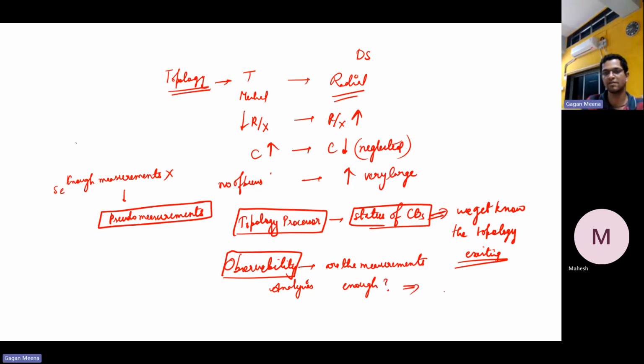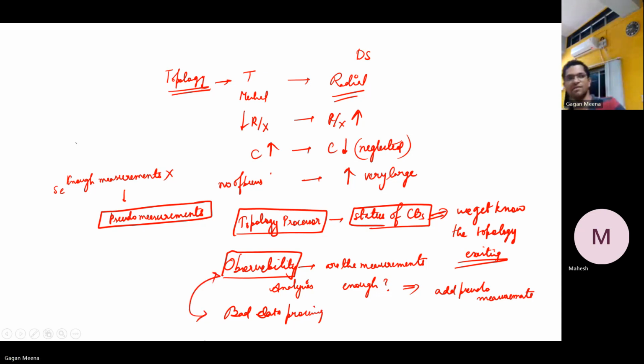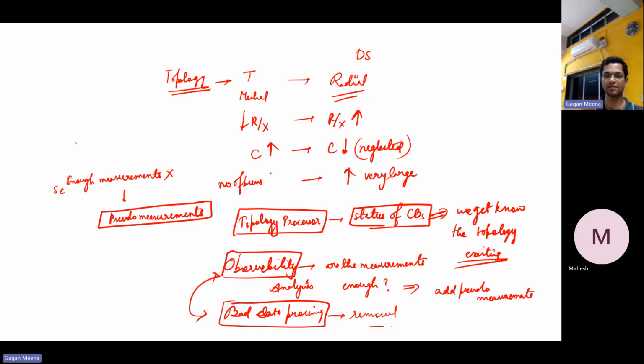If not, then we add pseudo measurements. Otherwise, state estimation cannot work. We add the pseudo measurements and then we do the bad data processing. This will be going in a loop. After removing the bad data, again we need to check whether it is observable or not. The removal of bad data is done.